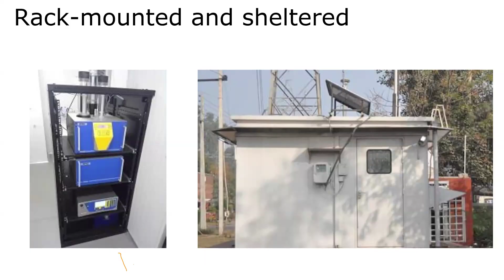Now every monitoring method or measurement method will have its positives, negatives, pros and cons, trade-offs, limitations, everything. The amount of accuracy and precision that these instruments' data have always comes with a cost. These instruments are generally costly, not only in the initial cost but also in the maintenance cost. Both the operating cost and capital cost, capex and opex, are high, because in earlier slides I mentioned that these instruments need regular calibration and routine maintenance. They also need some consumables to operate. All this adds up to the cost. The initial cost is also high.